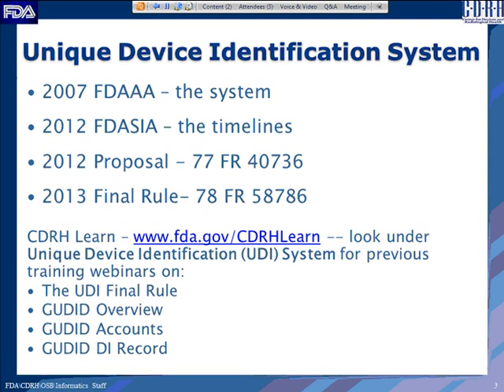The Unique Device Identification system was started in 2007 through the FDA Amendments Act, where Congress gave FDA statutory authority to establish a UDI system. In 2012, the FDA Safety and Innovation Act provided implementation timelines. A proposed rule came out in 2012 and a final rule was issued in 2013. We strongly recommend visiting the CDRH Learn portion of the FDA website for additional training and webinars on the final rule and an overview of GUDID.